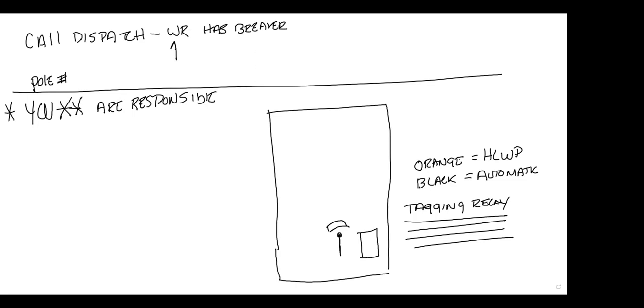Is that overload? Yeah, I've gone over. There's no fault, guys. There's no short circuits. There's no wires on the ground. There's nothing happened there. But I've gone over the load limits of that piece of equipment. Now I'll ask this question again. What is breaker overload? Over the limits of amps load on that piece of equipment. There you go. Exactly. I've gone over the limits, the capabilities of the breaker in load. I'm in breaker overload. You're thinking too hard on this.